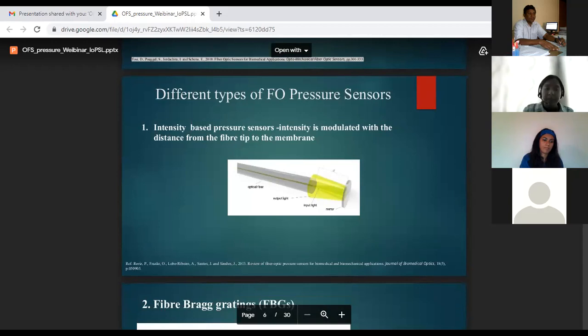Fiber optic pressure sensors can be broadly categorized into three main types. The first one is the intensity-based pressure sensors. These were probably one of the first pressure sensors to be commercialized. The working principle is fairly simple, and it is based on the variation of light intensity, or amplitude. As you can see in this picture, an optical fiber has its tip placed in front of a movable reflecting membrane. The optical fiber guides the light from the source to the tip of the fiber, and under the influence of the measurand the membrane's distance to the fiber tip changes, and hence the intensity of the reflected light coupled back into the same fiber can be modulated. Or, if you like, you can have another fiber parallel to this one.